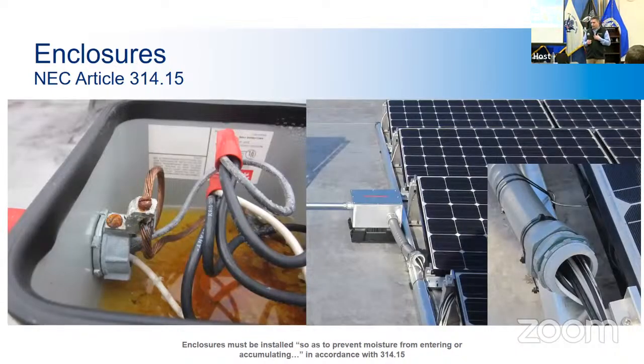there. Here we have an enclosure that not only has water, you know, standing water inside of it, which I would never tell you is a good thing, obviously. It also doesn't have outdoor rated equipment installed. You can see the wire nuts used are not outdoor rated, and specifically this ground lug and the screws are not rated for an outdoor environment. They're rusting, eventually they're going to snap right off. And then you have, you know, an ungrounded system.